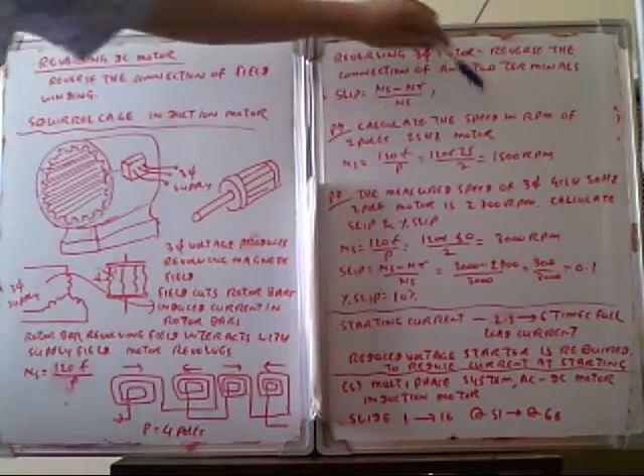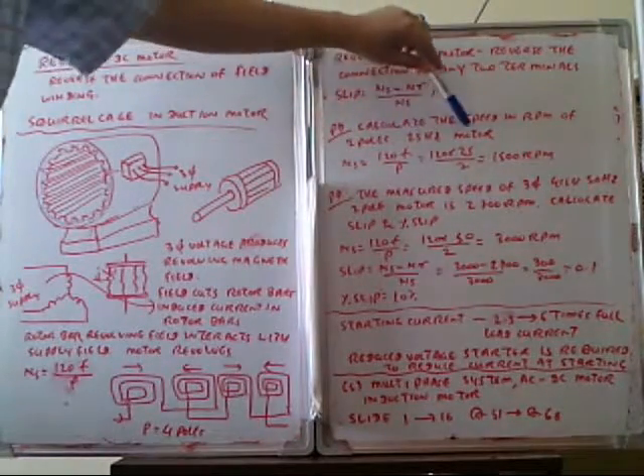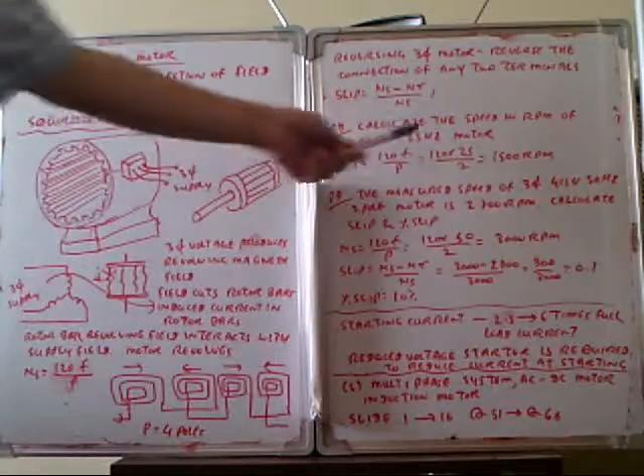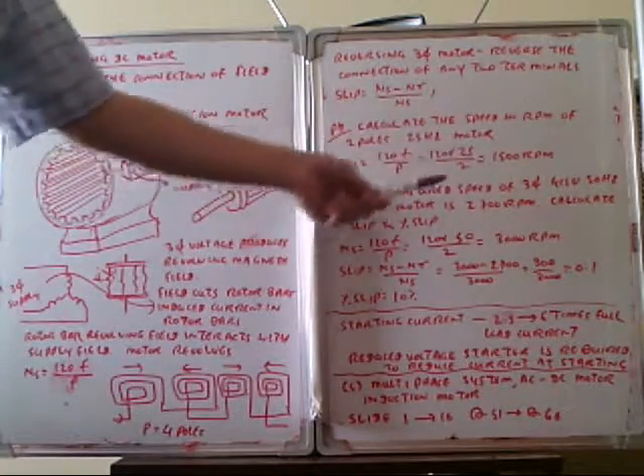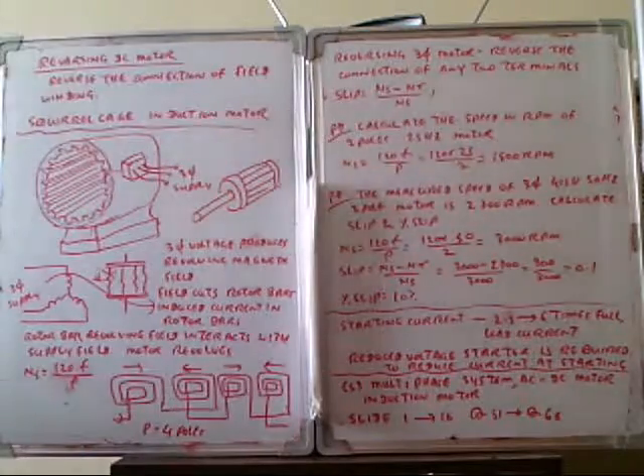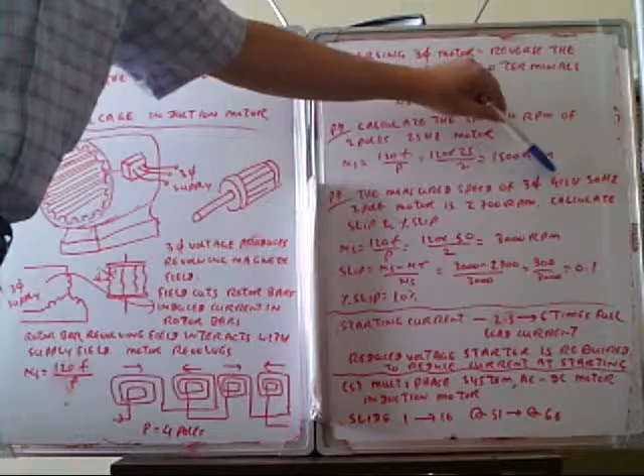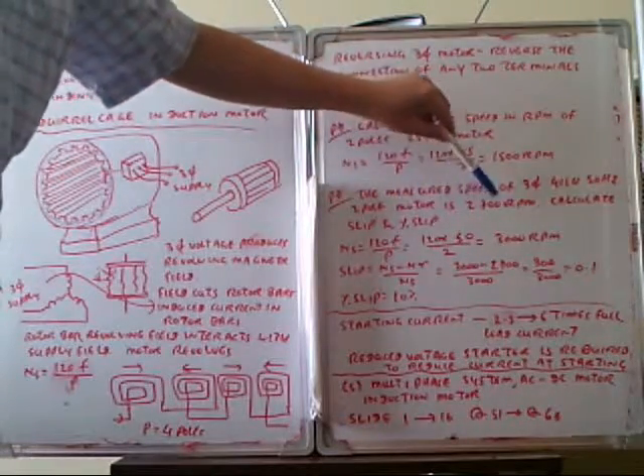We calculate this problem: calculate the speed in RPM of the two-pole three-phase motor. We write down the equation ns is equal to 120 f over p. So 120 multiply frequency 50 divided by 2, so we calculate 3000 RPM.